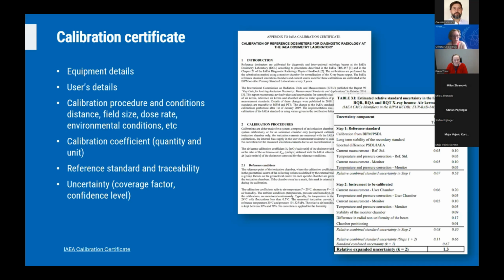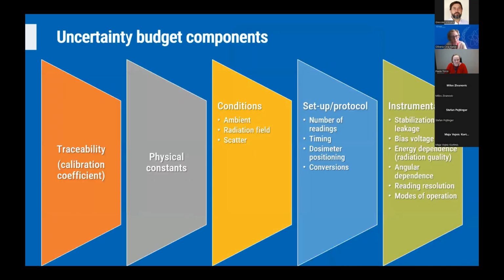Another mandatory part of the calibration certificate is information on the reference standards and traceability. In many instances, this additional information comes as an appendix, and in this slide you can see an example of the appendix to the calibration in the IAEA laboratory for diagnostic radiology calibrations, along with an example of uncertainty budget, and this is available from the agency website. Traceability information or calibration coefficients is the first parameter or influencing quantity that contributes to the uncertainty budget of the measurements. Other parameters that contribute to the overall uncertainty are related to the used physical constants, then conditions during the measurements, used measurement protocol and measurement setup, as well as the properties of the instrumentation or dosimeters used during the measurements.